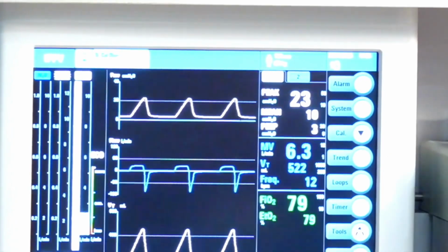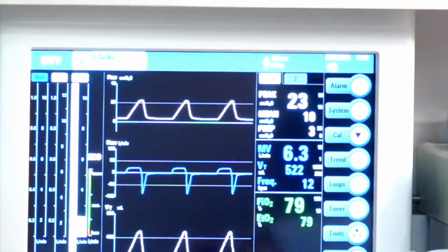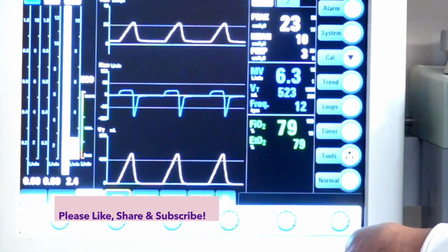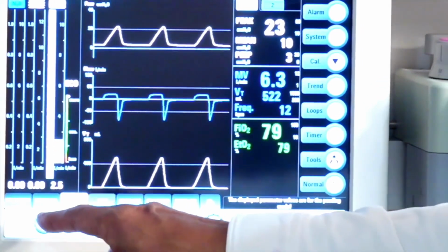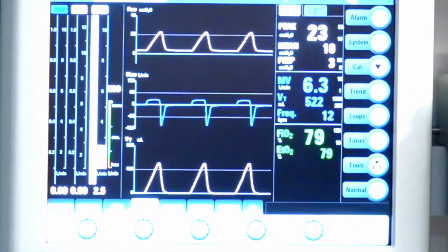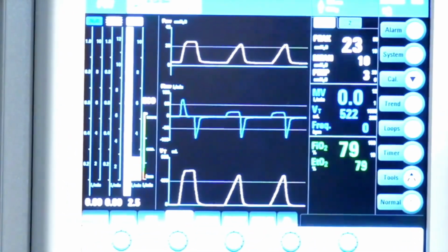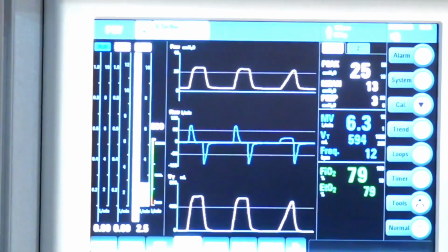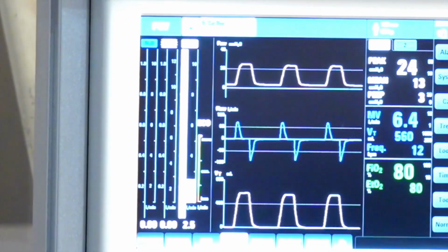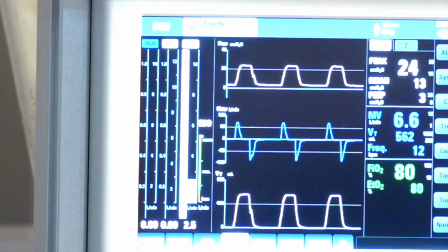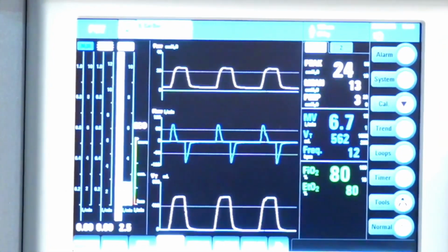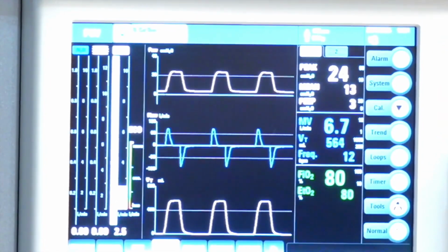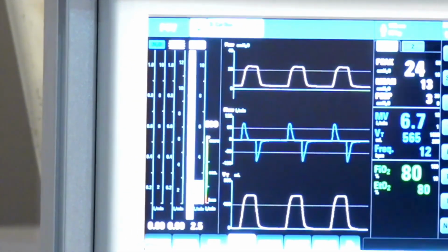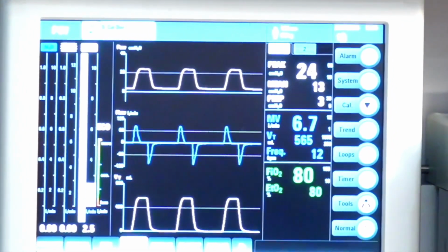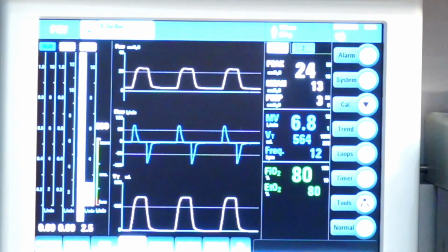Okay, now when we change over to pressure control ventilation, right now the peak pressure is 23, PEEP is 3. So let us put the pressure control ventilation, and the target is 23. Okay, perfect. Let me put it. Can you see the rise in the flow? The pressure control ventilation delivers very high flow initially. Okay, it has started giving more than 60 liter flow initially, and then it just needs to maintain that pressure. The idea is to have a pressure which is maintained. So it is called a decelerating flow pattern, because it delivers a higher flow rate initially, and then it gradually reduces because it is just maintaining that pressure for that particular time. So when you compare volume control with pressure control at similar peak pressure, pressure control is likely to deliver a higher tidal volume.